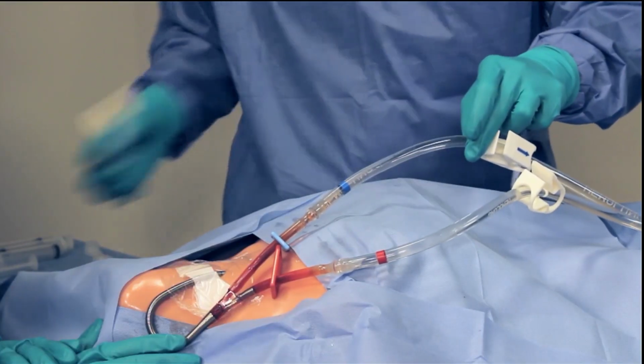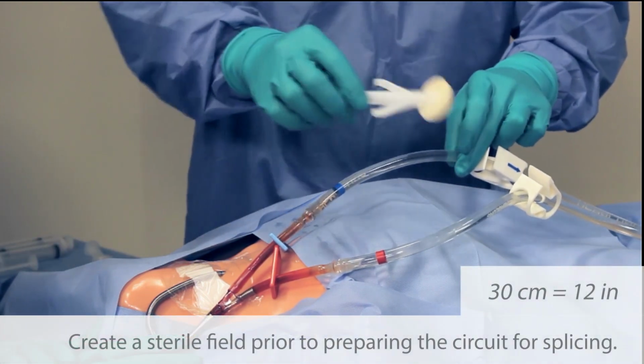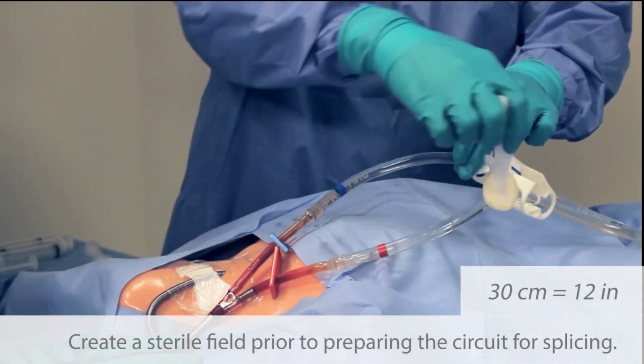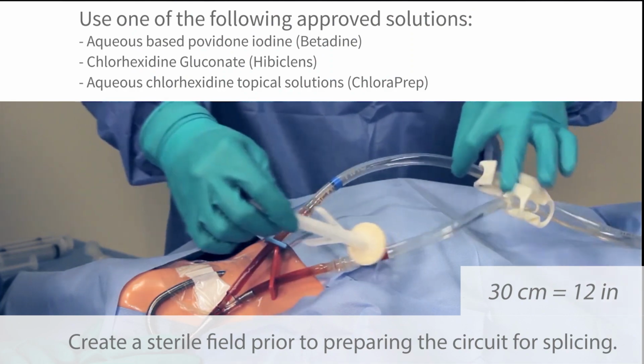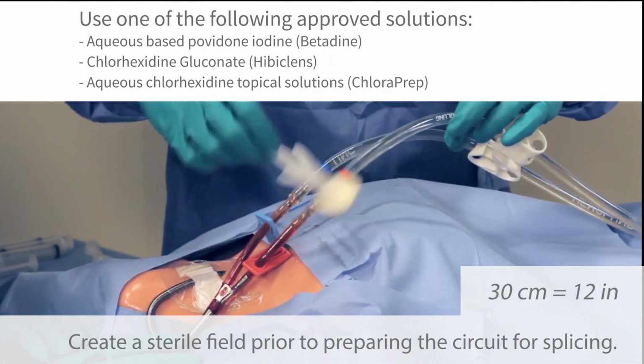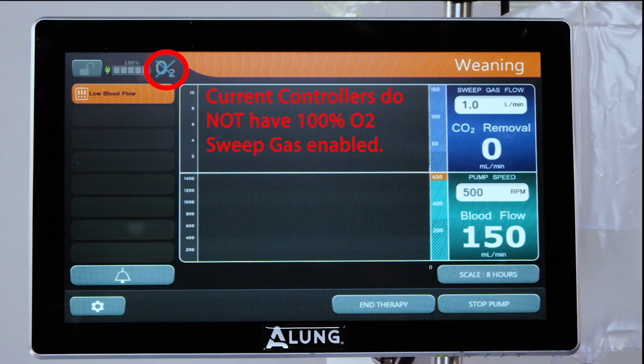Next, clean and disinfect a 30 centimeter length of each blood tube, starting at the catheter barb connector and moving towards the cartridge. Reduce the pump speed to approximately 500 revolutions per minute. Press the Stop Pump button to stop the pump.